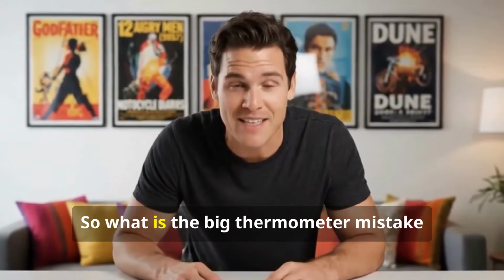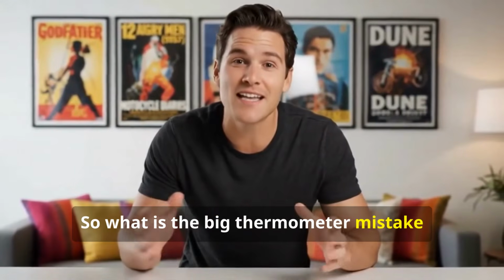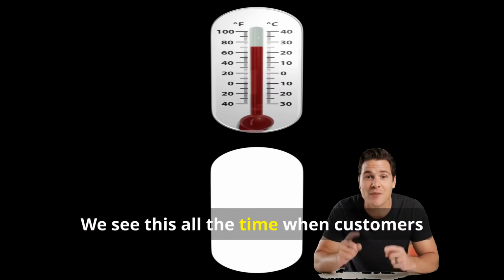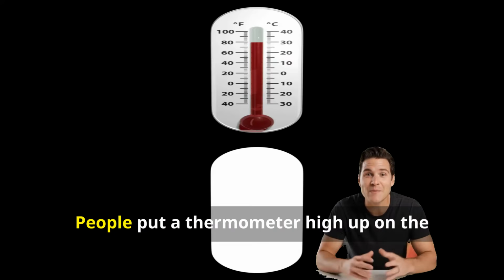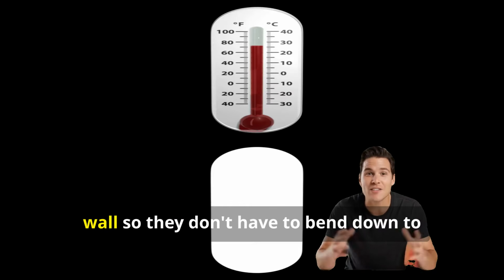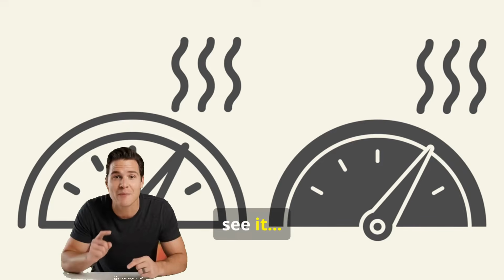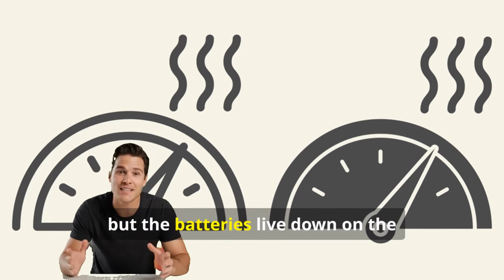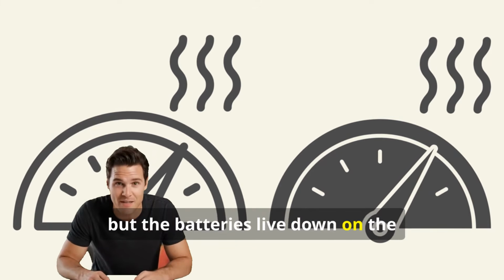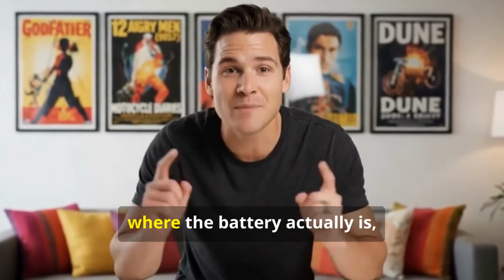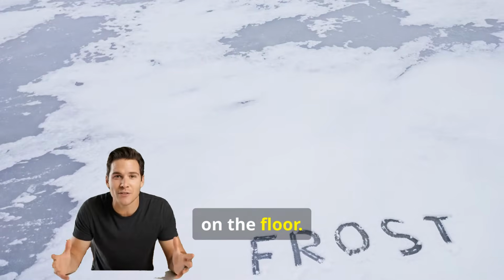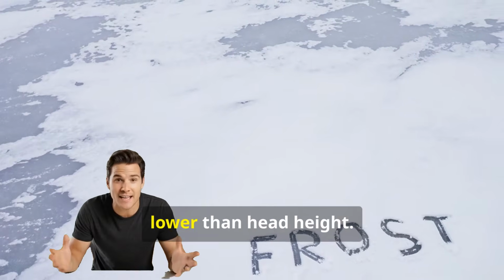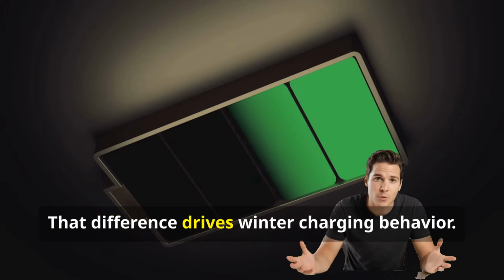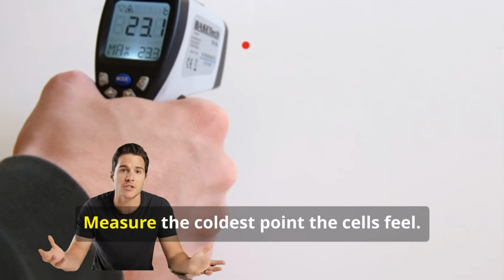So what is the big thermometer mistake everybody does? We see this all the time when customers measure temperature. People put a thermometer high up on the wall so they don't have to bend down to see it. But the batteries live down on the floor, and heat rises. So you need to measure the temperature where the battery actually is, on the floor. Floor temperature can be many degrees lower than head height, and that difference drives winter charging behavior. Measure the coldest point the cells feel.